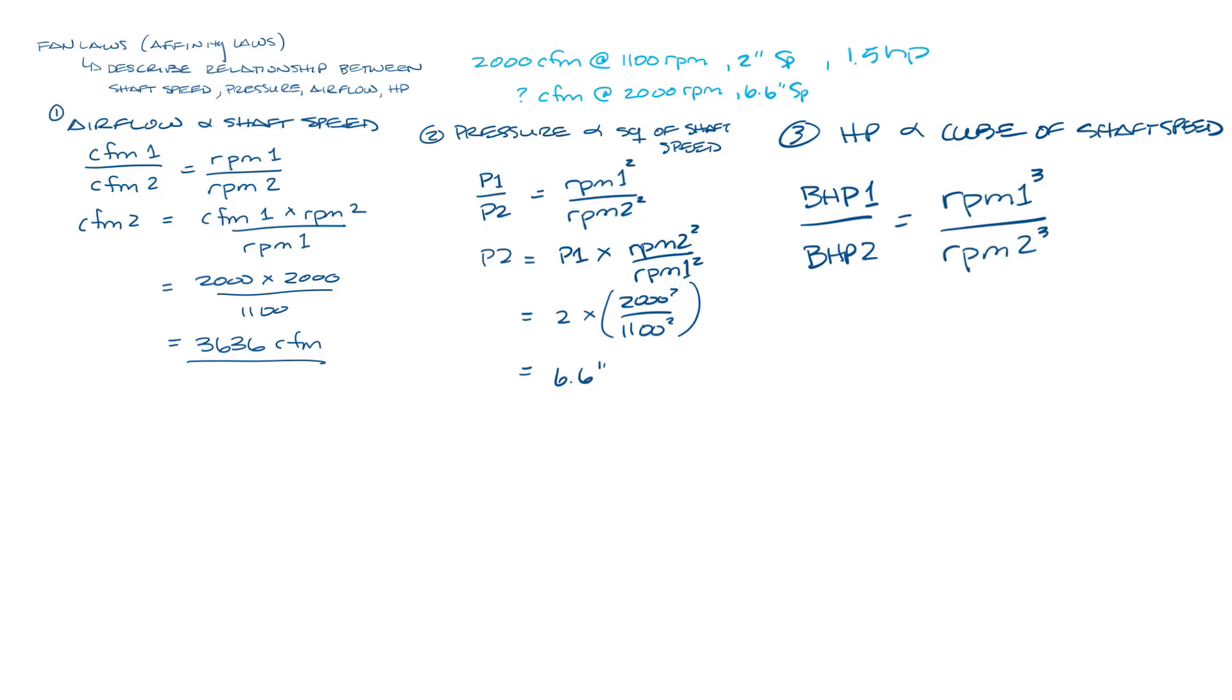So let's just say this is a one and a half horsepower motor. We get our equation for brake horsepower 2 equals brake horsepower 1 times RPM2 cubed over RPM1 cubed. Plug in 1.5, 2000 and we get about 9 horsepower.